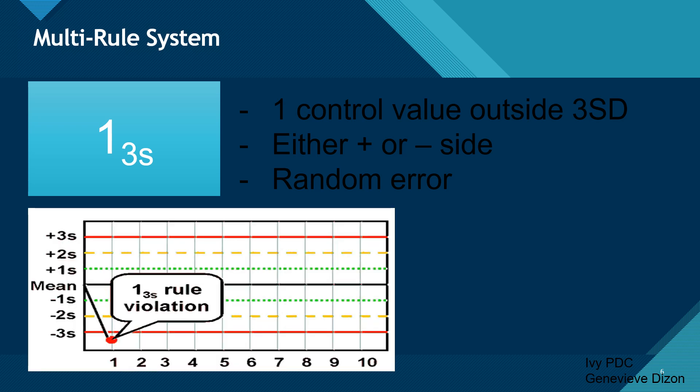The second rule is the 1-3-S rule, which means there is one control value located outside the three standard deviations. It can be either on the positive or negative side, and this is also considered a random error. If our data is outside the 3-SD, this is a violation of the 1-3-S rule. If we have a 1-3-S violation, we need to reject the results — we can't continue with testing. We need to reject the results that were run together with this control, because a 1-3-S identifies an unacceptable random error and may also be the beginning of a very large systematic error.